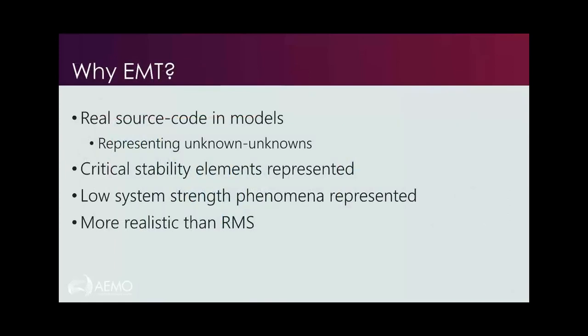So, why do we use electromagnetic transient models? They allow us to use the real source code in models — manufacturers take the code used on actual inverters in the field, put a wrapper around it, and give it to us for our modelling programs. We have the exact same code as in real inverters, meaning we can represent basically any unknowns, model the plant exactly as it operates in the real world, and model critical stability elements around low system strength. It gives us a more realistic view than RMS simulations. EMT is not better or worse than RMS — it's a different tool that solves different problems.